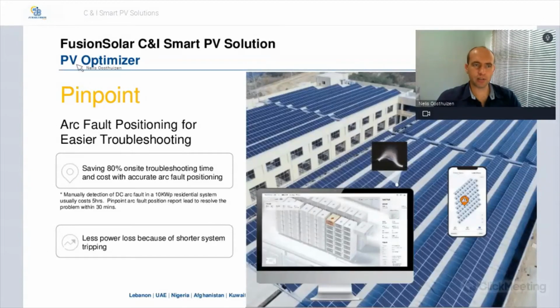I would like to add a note: if you want to see pinpoint for a full installation, then you do need to have each and every module fitted with an optimizer. Otherwise, again, you will just be notified of a specific string, and then you will still need to identify on that string, which module it is. But definitely, it is a lot simpler. You don't have the expenditure of adding optimizers on each one, but the optional availability is there if it's a specific requirement that you do want. So if you do a full optimized solution, you can have a saving of up to 80% on on-site troubleshooting time and cost of accurate arc fault positioning.